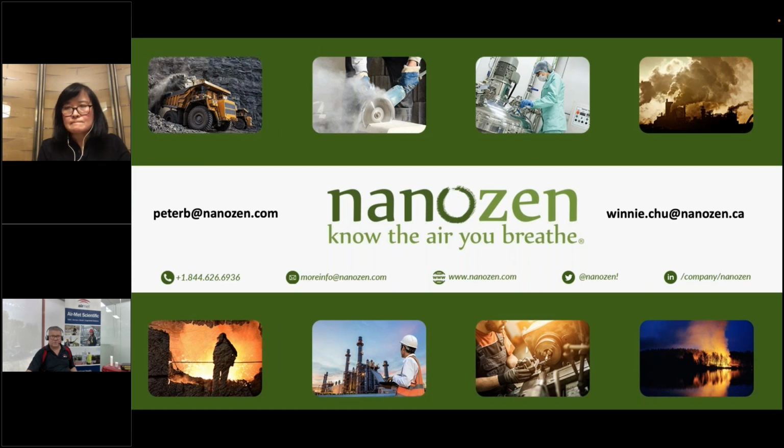Thanks, Winnie. So what's the difference between 3-litre normal gravimetric sampling pumps and 1 litre per minute for Nanozen? The pump depends on what kind of cyclone you are using for silica. The DustCount itself is 1 liter per minute. Our new SAS right now is only running 0.5 liters per minute. Cyclone, depending on which cyclone you use, is 1.7 or 2.5 liters per minute.